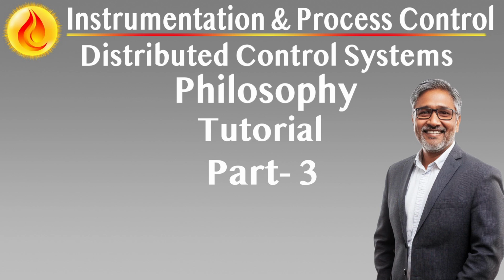Voting logic for fault tolerance and nuisance rejection. Apply 1oo2 or 2oo3 logic configurations where false positives are likely, especially for open path or IR flame detectors exposed to environmental noise. Voting schemes are dynamically visualized for operator transparency, signal integrity, and loop supervision.